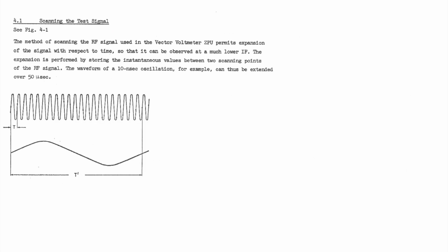And as I explained in the manual of the device, what we're actually doing is we'll take a high frequency signal and then we sample it using an impulse generator, which is creating very fast small impulses, and every time it is basically sampling the input signal, and doing that at a rate that is a multitude lower than the incoming frequency. We basically can create an IF signal that respects the original amplitude, the waveform, the phase differences and the harmonics of the original incoming signal.